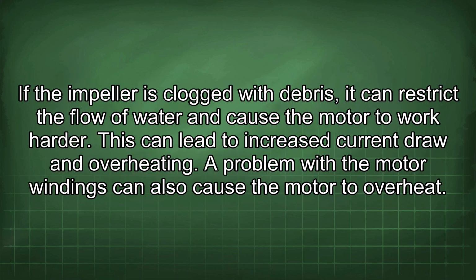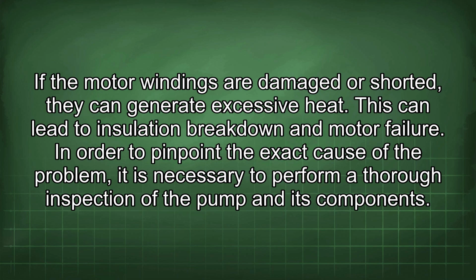If the impeller is clogged with debris, it can restrict the flow of water and cause the motor to work harder. This can lead to increased current draw and overheating. A problem with the motor windings can also cause the motor to overheat. If the motor windings are damaged or shorted, they can generate excessive heat. This can lead to insulation breakdown and motor failure.